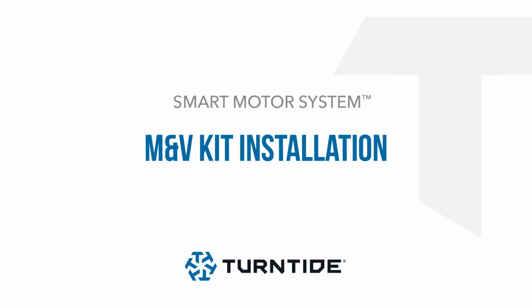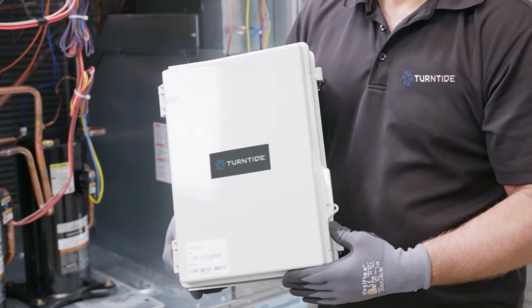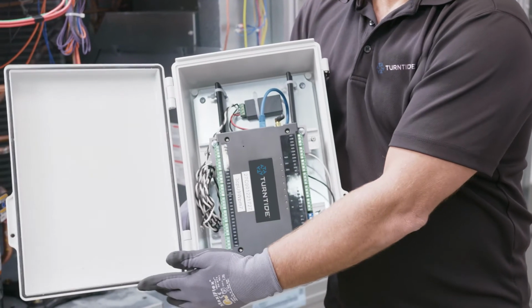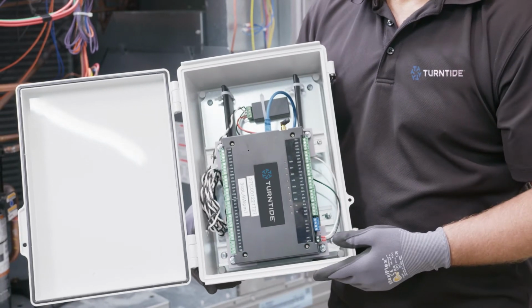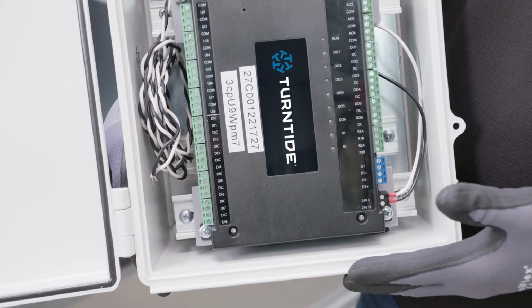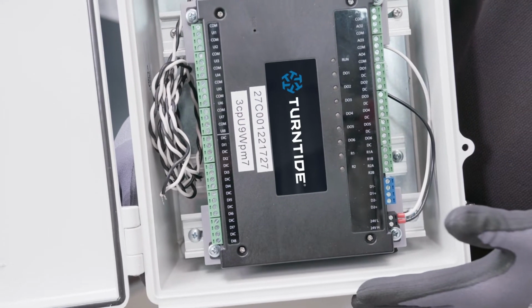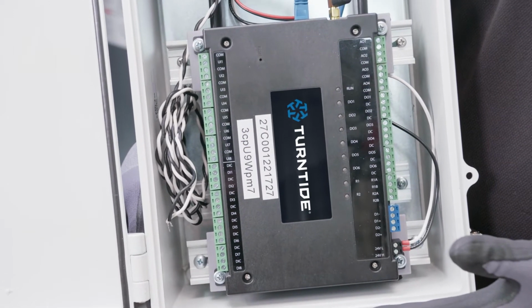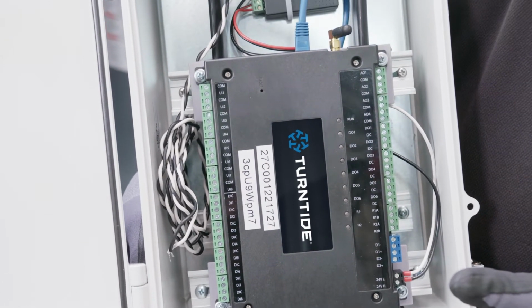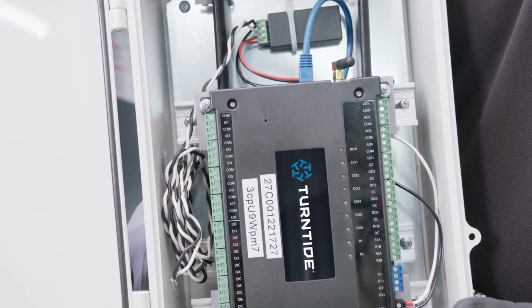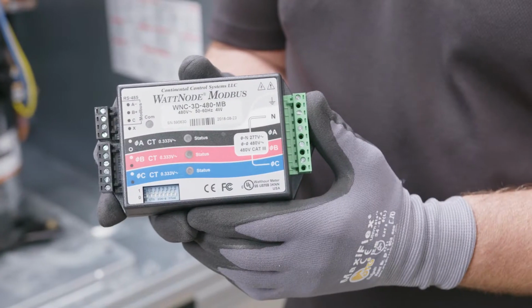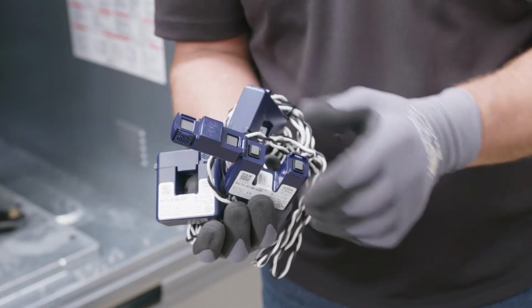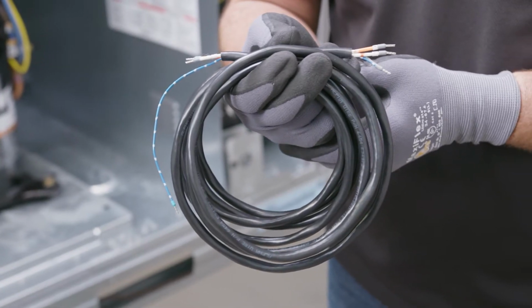In this video, we're going to cover the Measurement and Verification Kit, or M&V Kit. One good use of the M&V Kit is to capture energy performance data, which can allow you to compare the existing induction motor's operational efficiency to the smart motor system. The M&V Kit is comprised of a weatherproof enclosure, which comes with a supervisor, a wireless modem, a power meter, 3 current transducers, and a modbus communications cable.